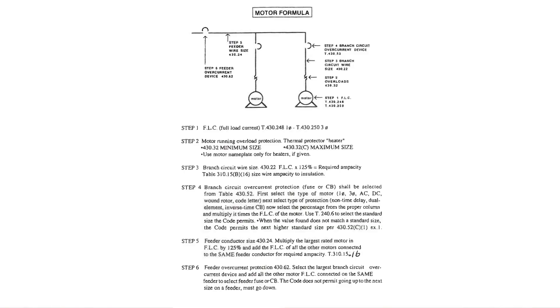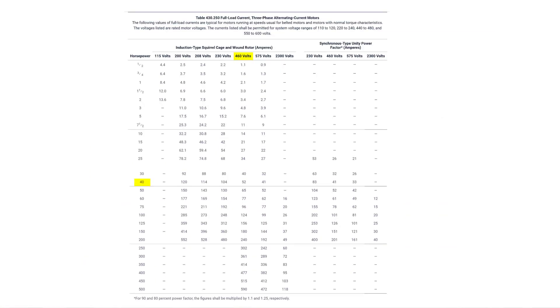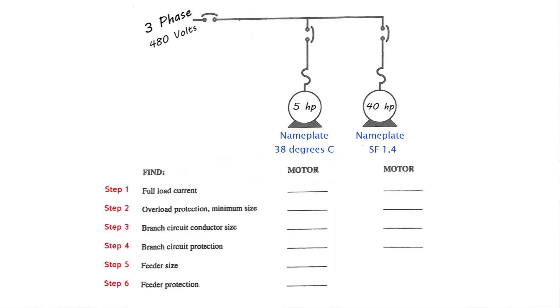So what is step number one in our six step format? Step number one, we're dealing with 480 volt three-phase. We're looking at the 430.250 table. What is the horsepower at 5 horsepower? What's the amp capacity, the full load current? 7.6 amps. And for a 40 horsepower, the full load current is 52 amps. That's step number one. That's not hard, right? That's just looking at a table, picking information off of the table.